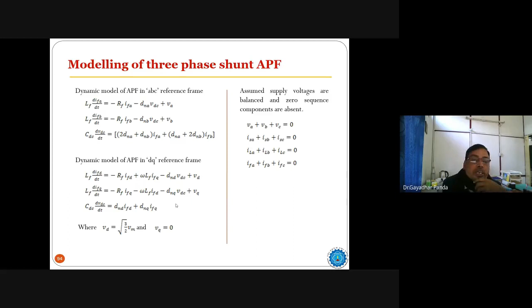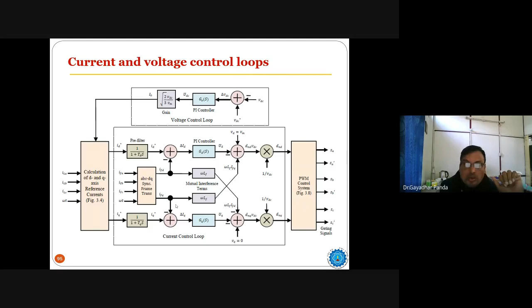We are particularly collecting the feedbacks from the load side, and depending on those load currents, we are generating the reference signal. Reference signal means that is a compensating current. What should be the compensating current to be produced by the PWM inverter, so that it will eliminate the harmonics. And we know that we generally go for the DQ transformation, we convert from ABC to DQ, and the DQ makes the controller algorithm simpler. You can think of one as the active power component and another as the reactive power component, and based on that, control will be easier.